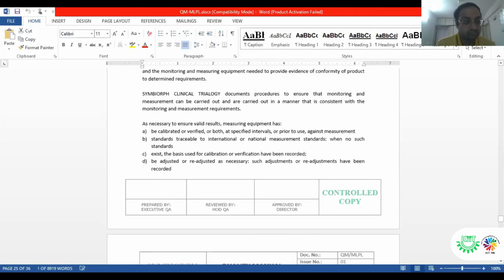We have a question from Mr. Sameer Karaz: to what extent will the ISO 13485 auditor investigate the design and development and other technical files of the medical devices? They can go in depth, as in depth as they want. But definitely they will not hamper your IP, because they have to sign an NDA or a legal document with you. In most cases they will cross-check with all the regulatory standards, whether you are fulfilling them or not, and all the requirement aspects of your design development clause 7.3, or as per the US FDA requirement, the waterfall method, whether you are fulfilling it or not.